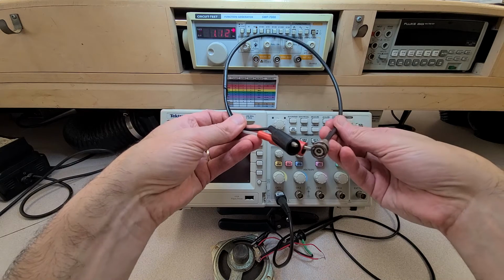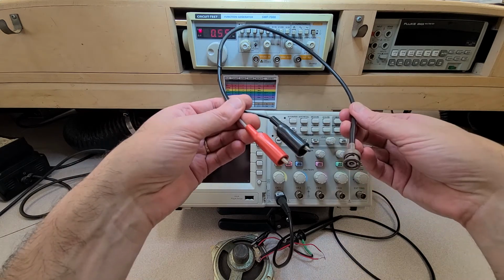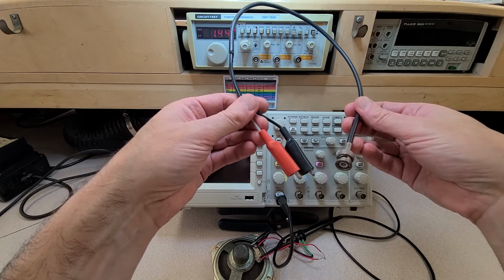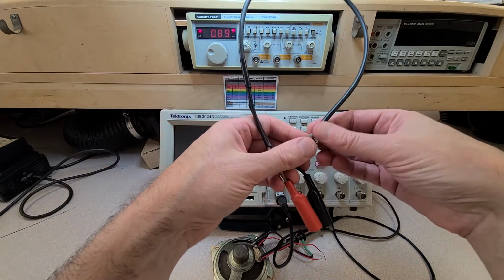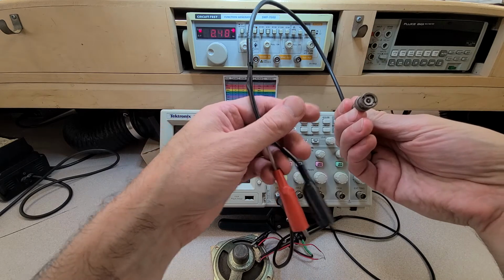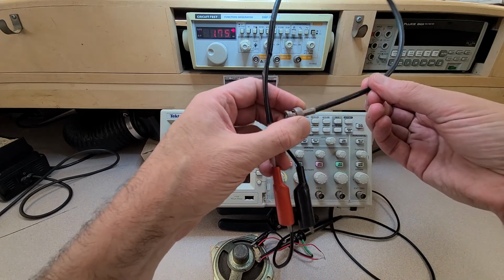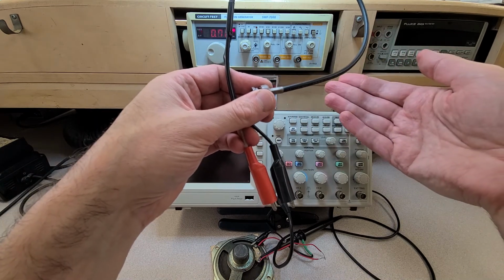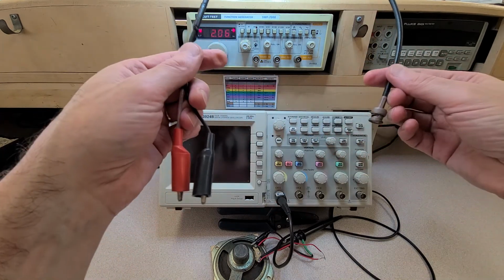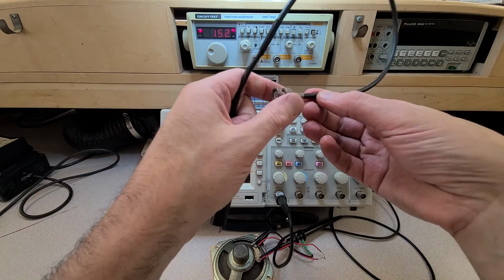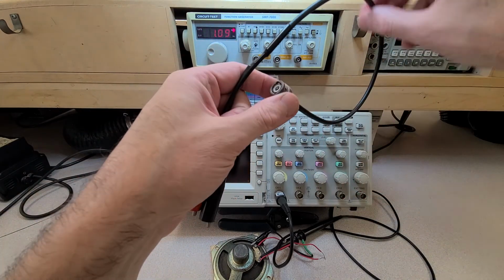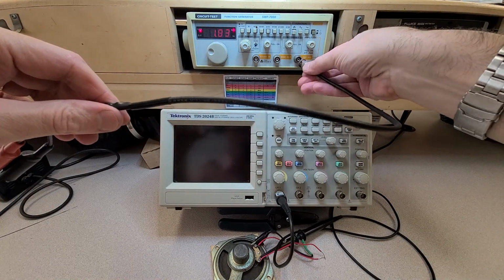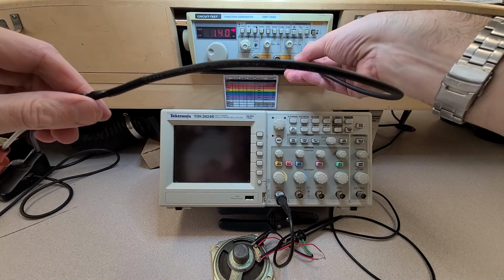And again, this cable comes in with a BNC connector, but instead of coming out like an oscilloscope probe to a fancy probe, this just comes out to a couple of alligator clips. And again, we're using the BNC connector and the shielded cable because at our high range of frequencies on here, we can get up into the radio frequency range, and we don't want to start transmitting radio waves unintentionally. By putting the shielded cable around the outside, that keeps the signal inside from acting like an antenna. This plugs into the ground.